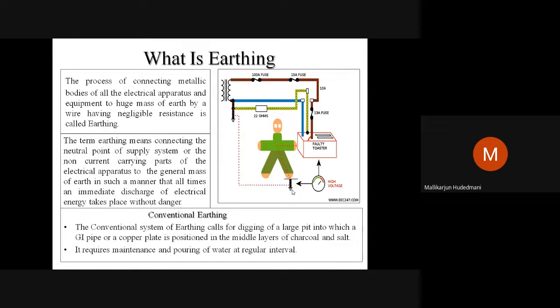Then how is earthing done? Just see this example. There is a transformer, and a toaster having one fuse: a very large 100 ampere fuse is provided, and another 15 ampere fuse is provided, and it is allowing the toaster to work. You can see here brown and blue are the two wires, and there is a greenish earth wire. Can you see this? Yes. A human is just touching this. The toaster is faulty, and the metallic enclosure is being touched by the operator who is trying to toast. Then the resistance which the earth wire has is about 22 ohms here. The greenish wire is shown here. You can just see this 22 ohms.